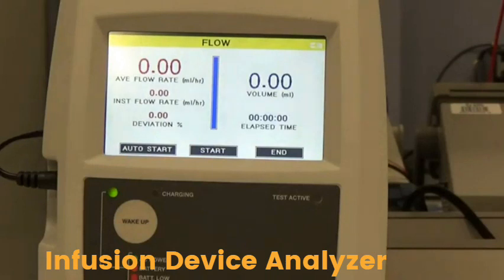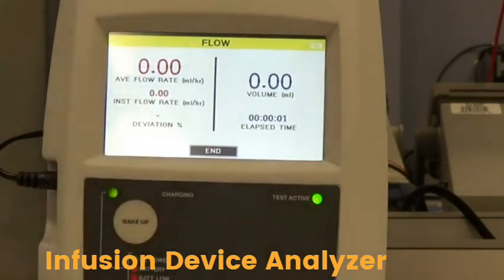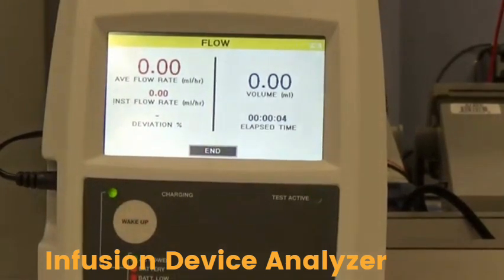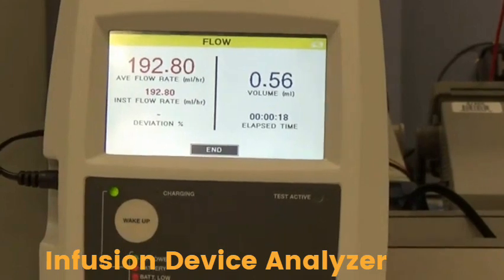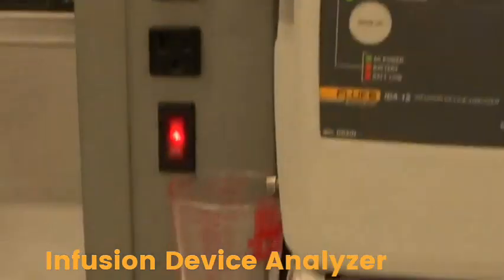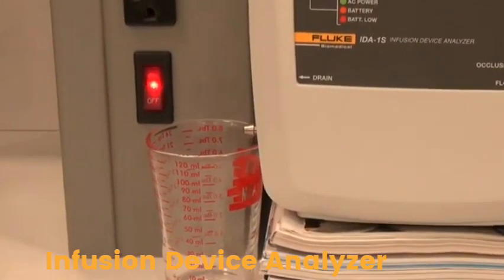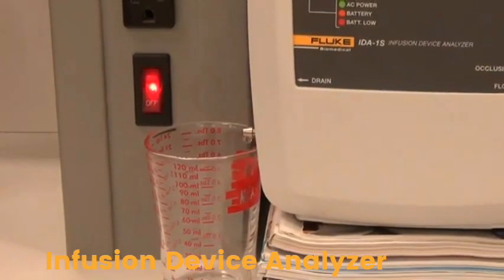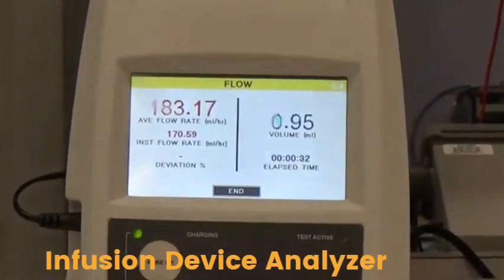So at this point, all we need to do now, I'm going to start my infusion device and I'm going to start the test at the same time. Start and start. You should see some numbers coming up shortly. That lets us know the device is currently functioning properly. And another thing we can do, we can actually test water dripping into our beaker. So this should take about 10 minutes. We'll come back here in just a few minutes and see where we're at.